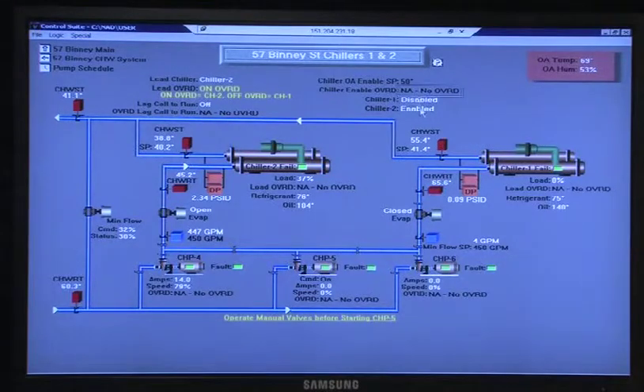Right now chiller 1 is disabled and chiller 2 is enabled. This chiller's running at 37%. You get the information off the chiller here. Refrigerant is at 76 degrees. Oil is at 104 degrees. Chilled water is coming through the chiller. We're watching the chilled water supply coming out of the chiller. It's at 38 degrees, and the set point is 40.